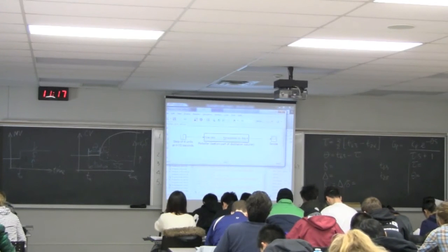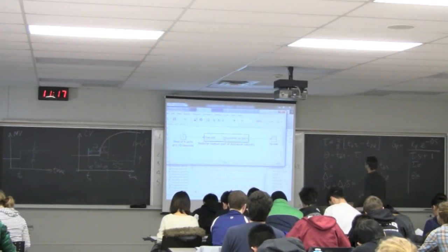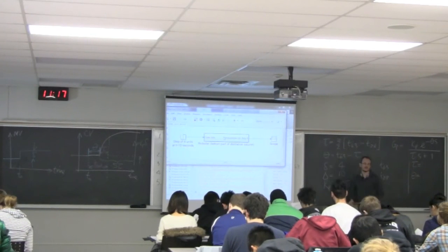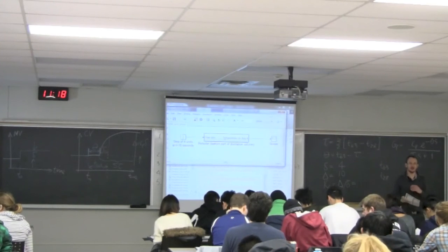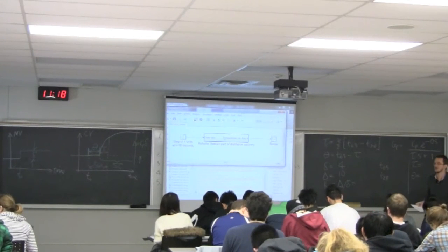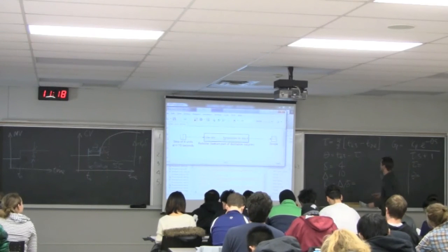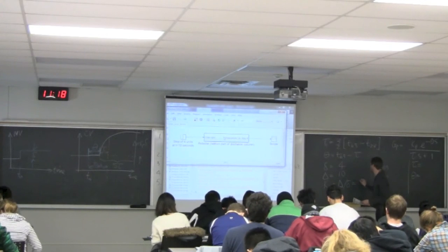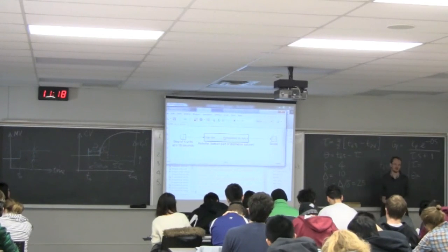Uppercase delta in this example? Four units, uppercase delta? 10. Okay? So the fact that we're at 74 degrees, 84 degrees, it doesn't matter. We're only interested in the deviation. So we made a 4-unit input change, we saw a delta of 10 units. What is KP? 2.5. So our gain for the system is 2.5 units.